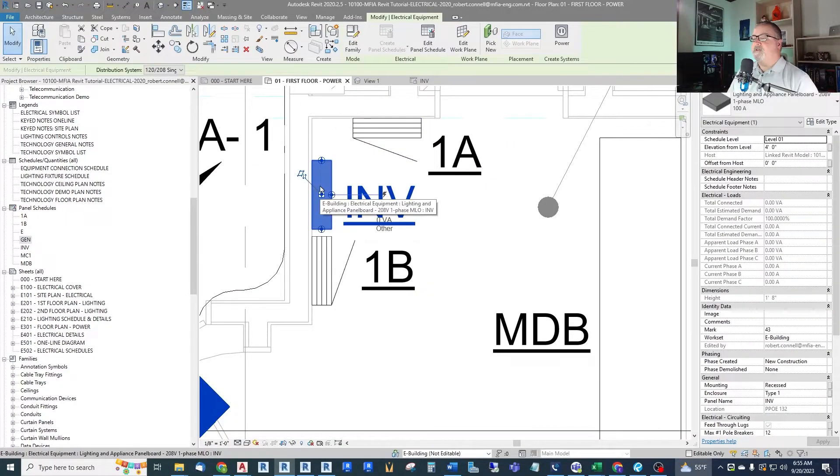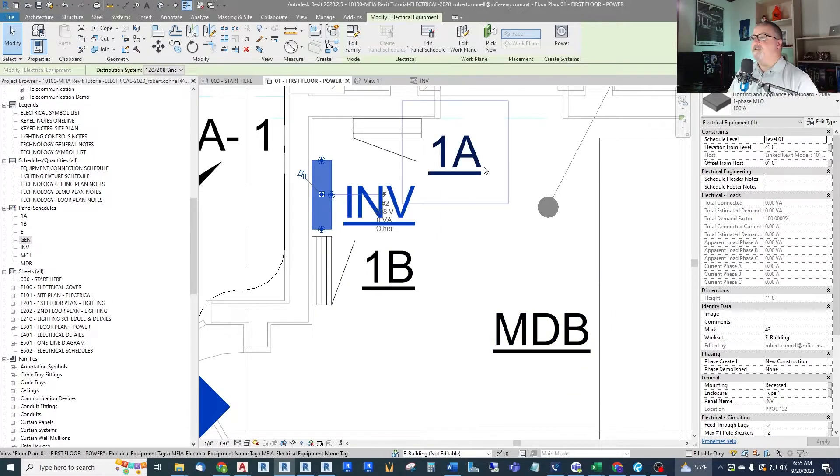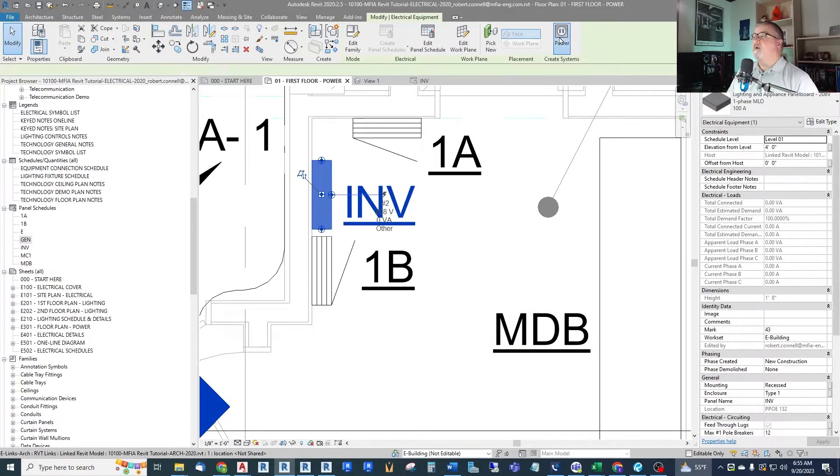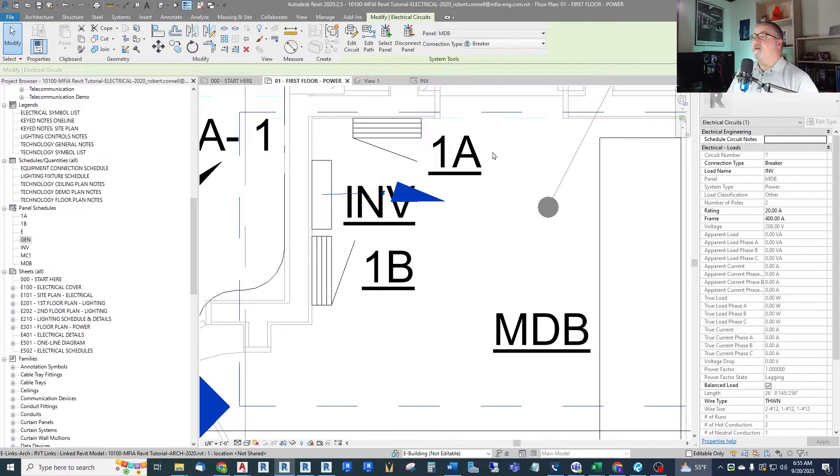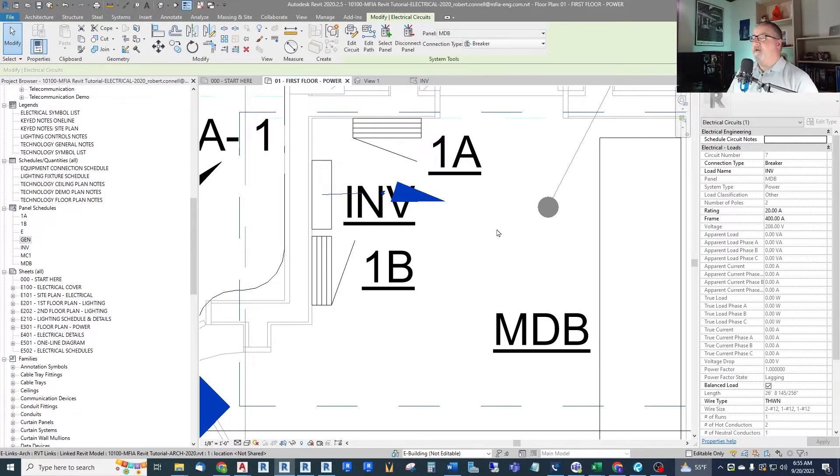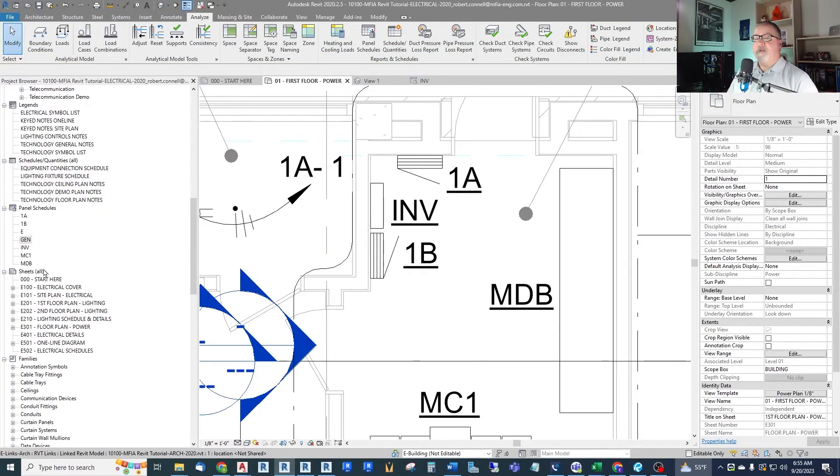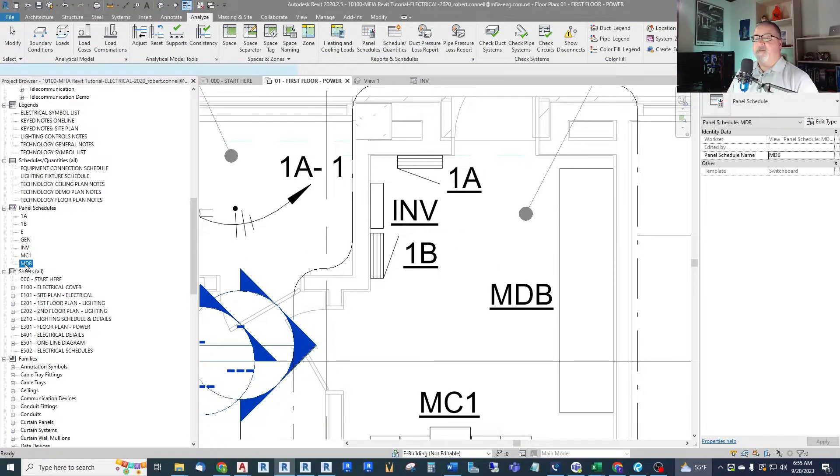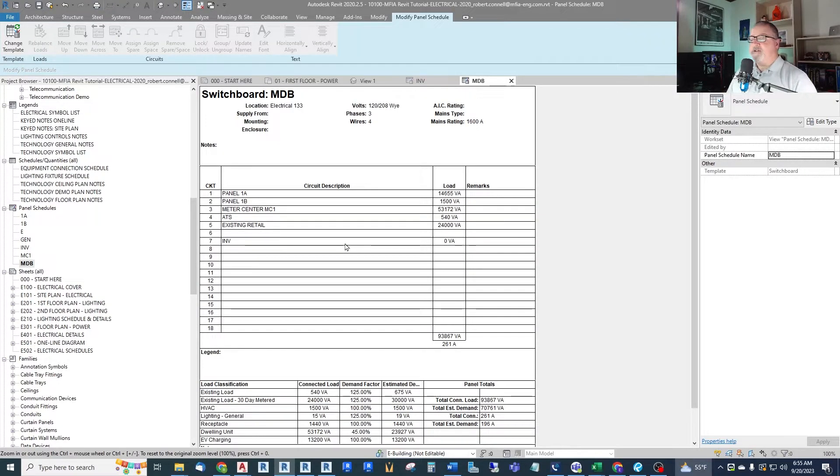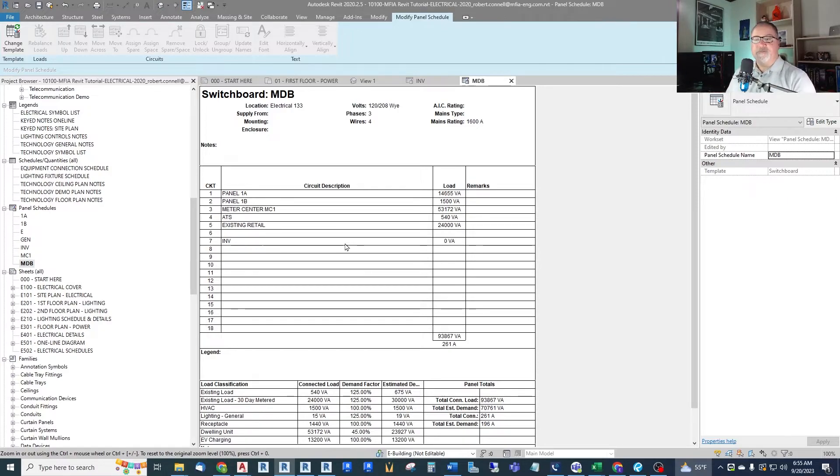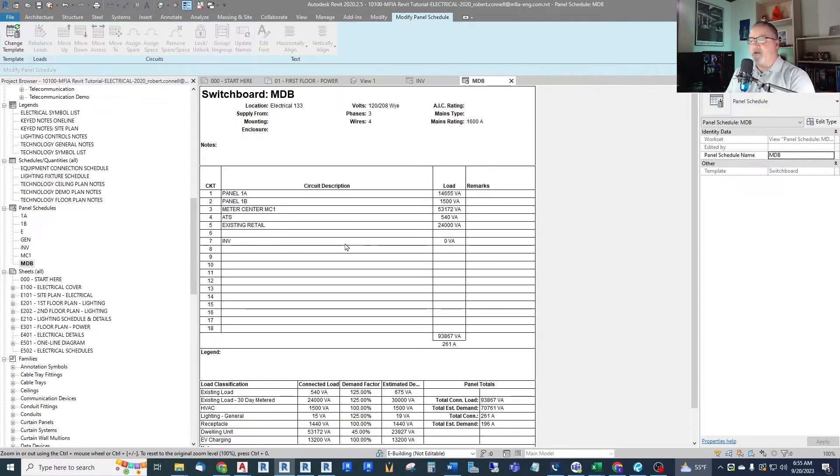But that is how we go about creating a single phase three-wire panel. And we can hook this up to our three-phase main distribution board. You will see that it comes up MDB. And there it is. It's in our MDB as the inverter. So it all connects to a three-phase system, even though it's a single phase panel. But it shows as only having two phases in it for calculation purposes.